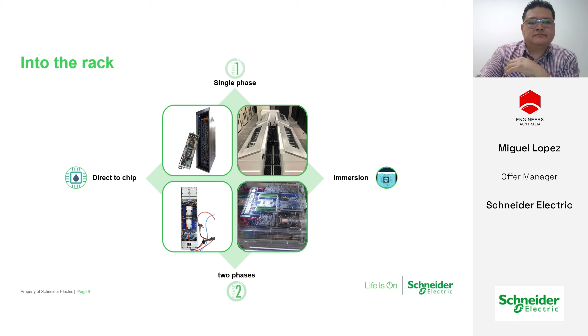As we saw with the recent announcements by NVIDIA, the heat densities are just never-ending, rising in a never-ending format. We have to arrive at so-called hybrid data center designs. These hybrid data center designs, first instance designed to be air-conditioned for air-conditioned servers, are now seeing a need to have liquid cooling brought into them as a result of the AI revolution. So this is revealing that direct-to-chip single phase is actually the front runner, as far as the medium for these liquid cool systems.